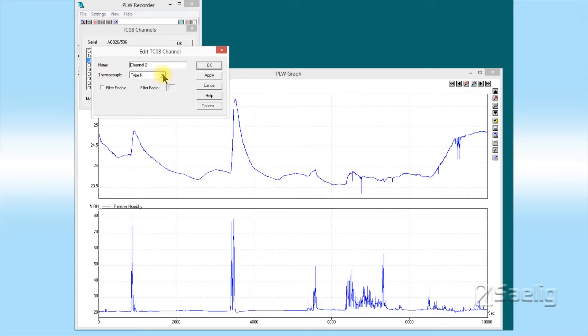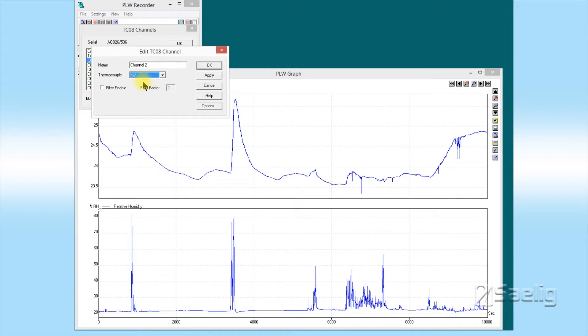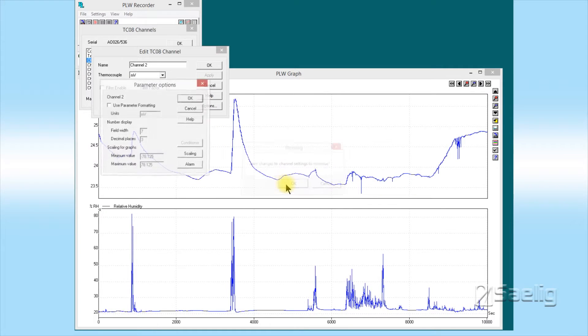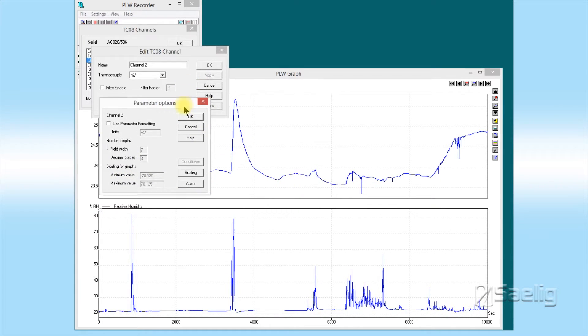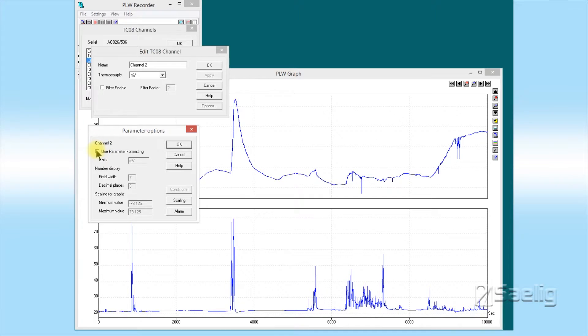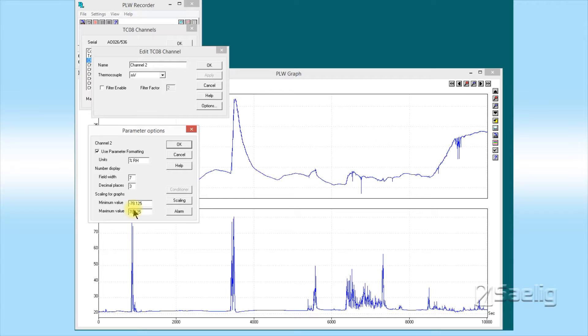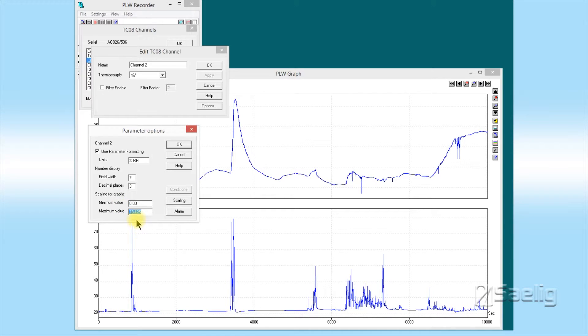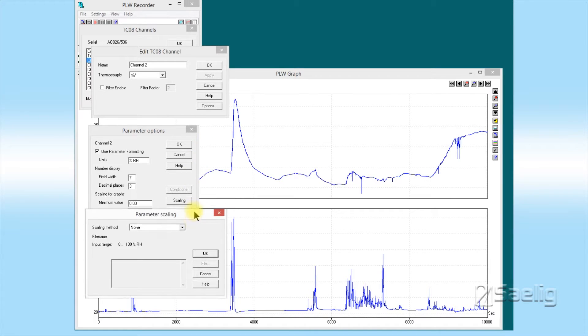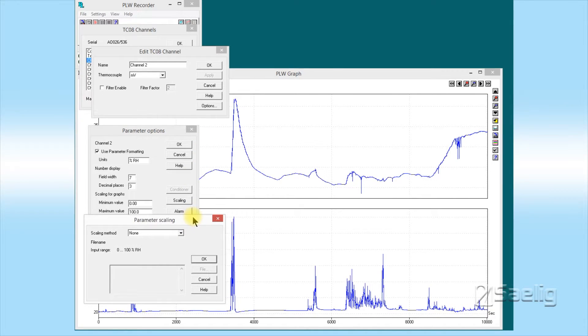Now we have to go to channel 2 and do the same thing for the relative humidity. So I say millivolts for that, go to options, use parameter formatting again. The unit is not going to be millivolts—it's going to be percent relative humidity, or you can just say RH, but let's just put percent RH for that. The minimum value on the humidity is going to be zero and the maximum value is going to be 100.